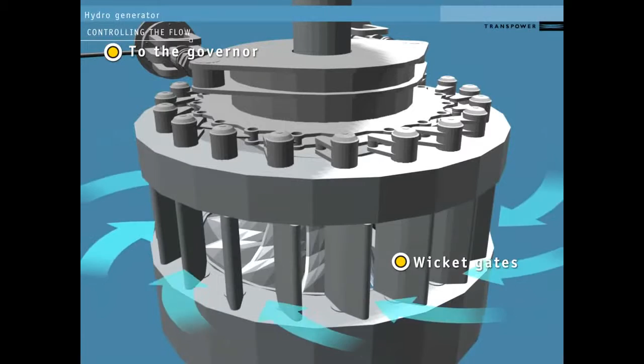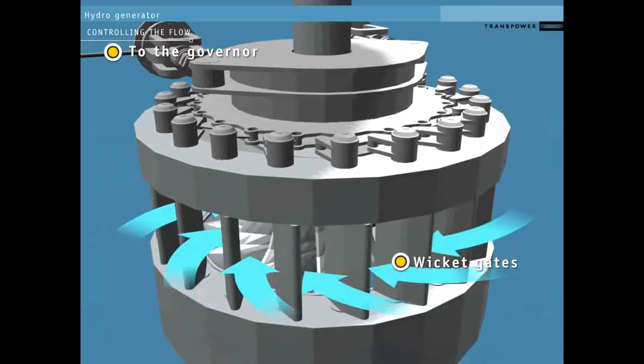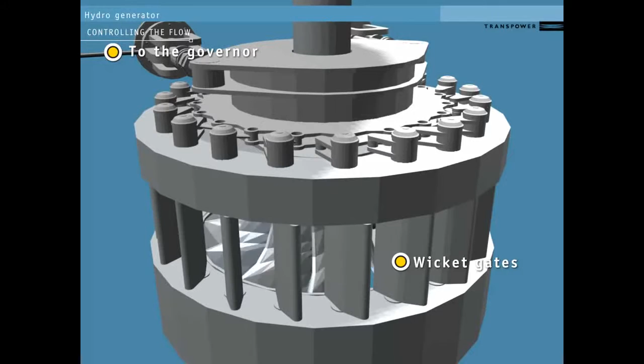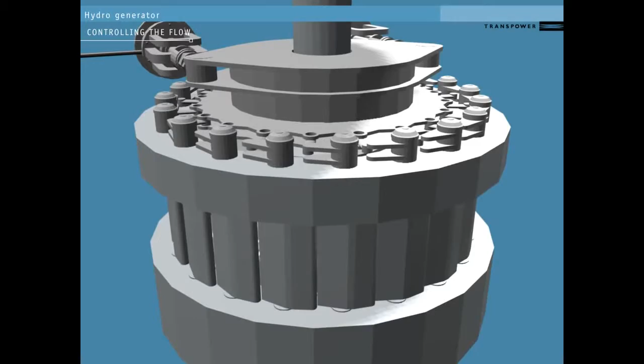The wicket gates are controlled by an external governor system. This opens and closes them in response to conditions on the national grid. A high load on the system slows the turbine, and the governor system reacts by opening the gates further to speed it back up. Conversely, it will narrow the wicket gates in response to low load on the system.